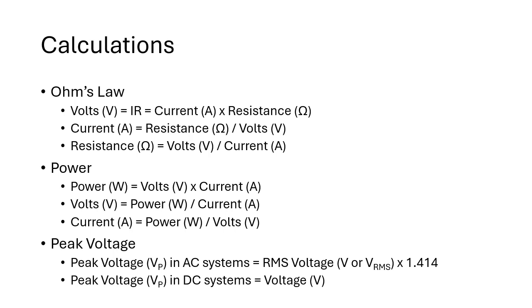So what I had was an AC system with 240 volts, and I wanted to put over voltage protection on that, so I needed to multiply the AC voltage by 1.414 to work out the actual peak voltage in order to calculate how much voltage my over voltage protection device needs.